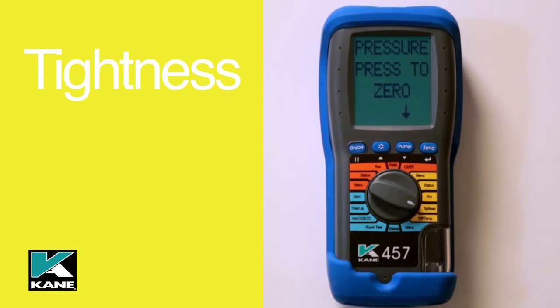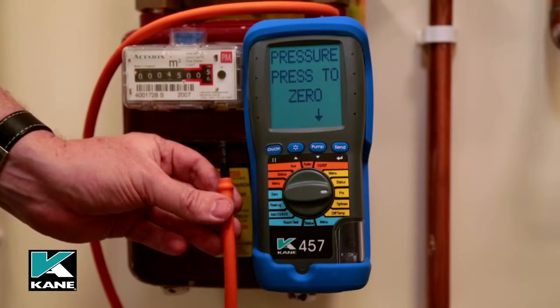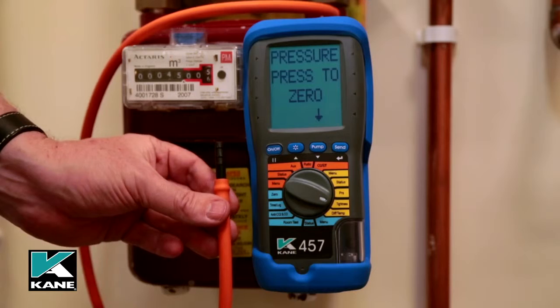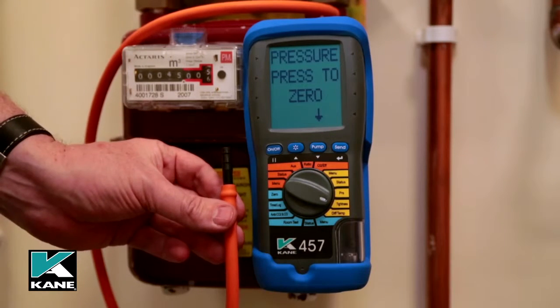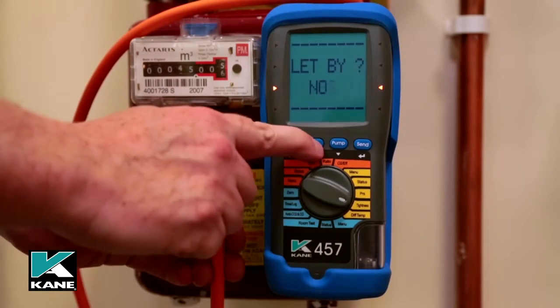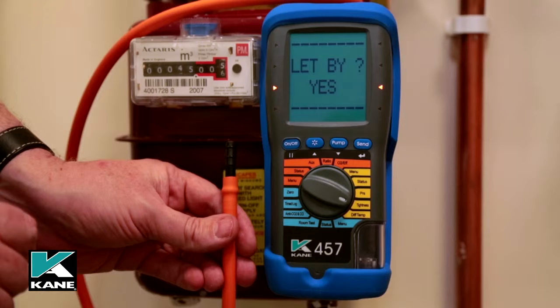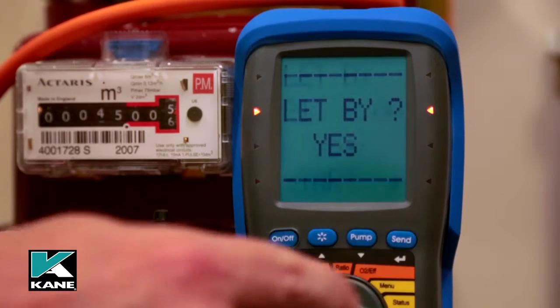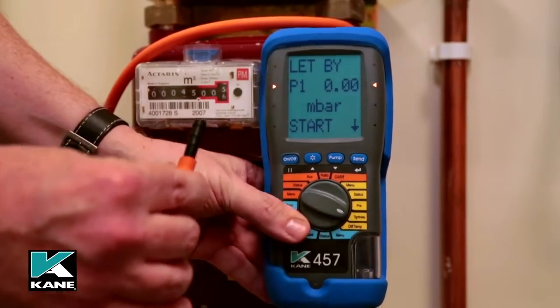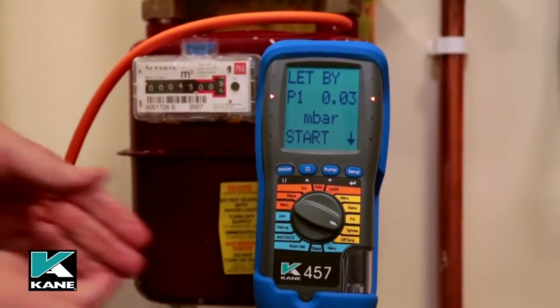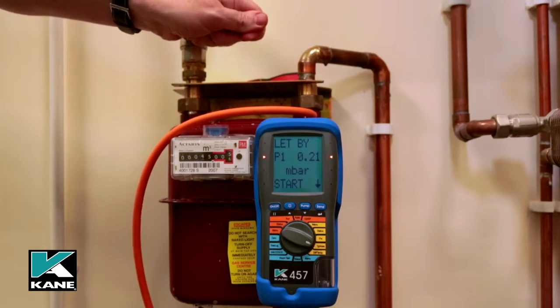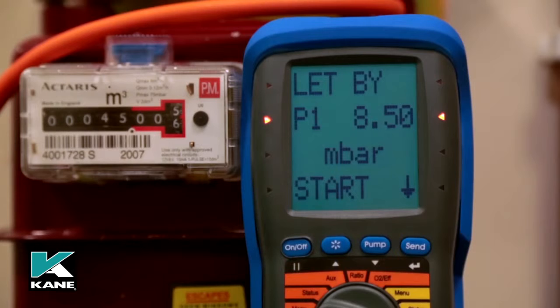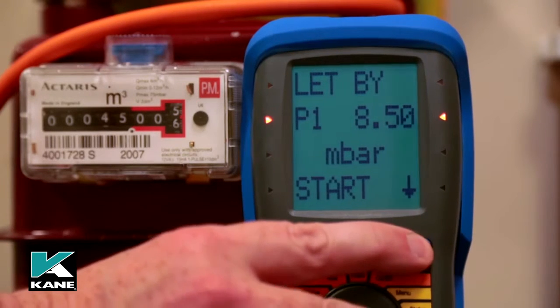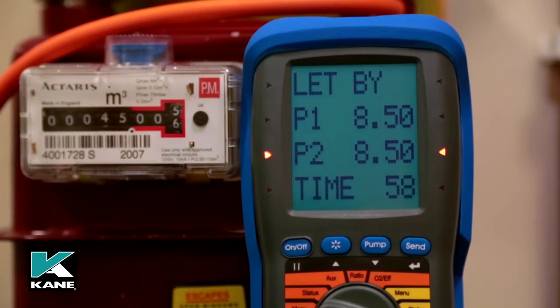The next position on the dial is a tightness test. To carry out the test, ensure the pressure hose is not connected to the analyzer and select tightness. The pump will stop. Press the pump button to auto-zero the pressure sensor to ensure accuracy. Select yes or no for the let-by test by using up or down key. Press send to confirm yes for a let-by test. Connect from the test point to P1 using a black connector and manometer hose. Adjust the gas pressure to between 7 and 10 millibar in accordance with IGEM UP 1B 3rd edition. Press send to start either the let-by test or the stabilization period.